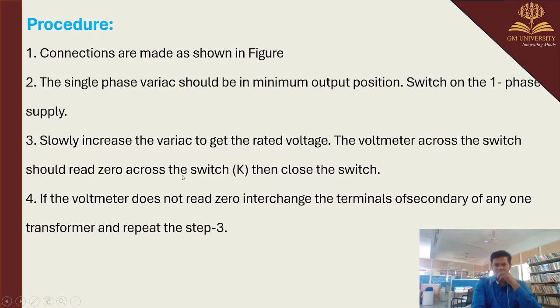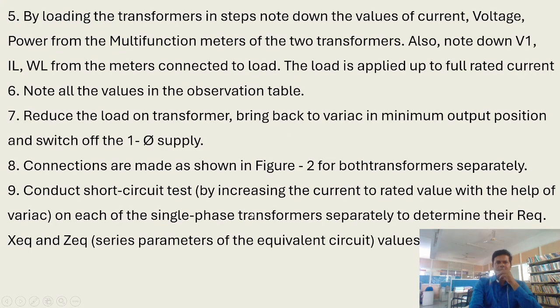So the voltmeter across the switch should read 0, then you close the switch. If it reads double the voltage, then you have to interchange the terminals of the secondary of one of the transformers, and then repeat step 3. Then, by loading, you apply the load to the transformers step by step and note the readings of voltage, current and power from the multifunction meter for the two transformers.